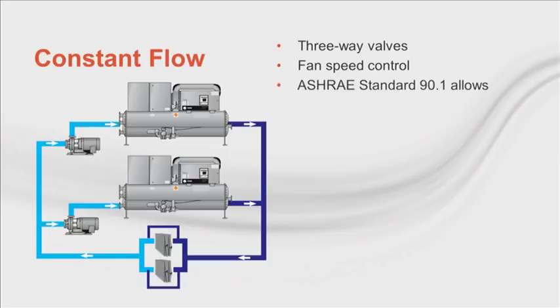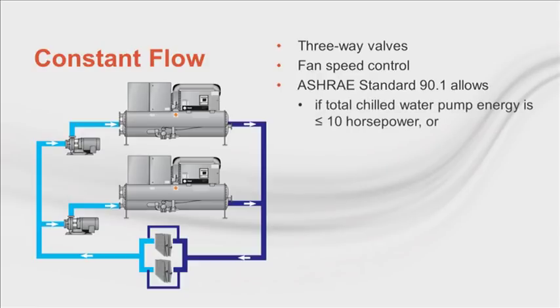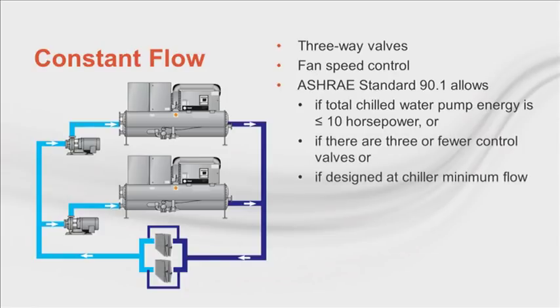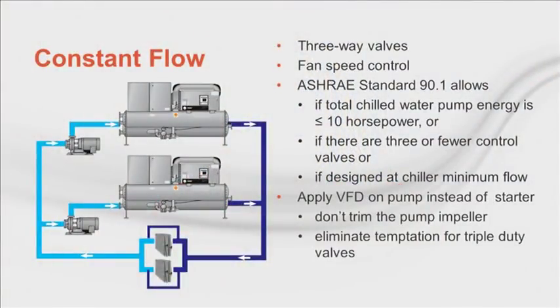Constant flow systems are allowed by ASHRAE Standard 90.1 when the total chilled water pump energy is 10 horsepower or less, or if there are 3 or fewer control valves, or if the system is designed at the limits of the equipment, and one limit is chiller minimum flow. Even though the flow is constant, a VFD can be applied to the pump motor in lieu of a starter, so you don't have to trim the pump impeller, and you won't have the temptation to put on a triple duty valve, as you no longer have the need for a balancing valve at the outlet of the pump, doing nothing for you but wasting energy.